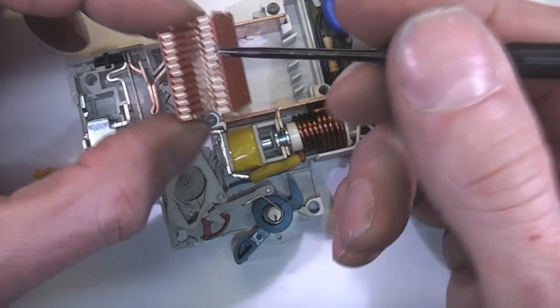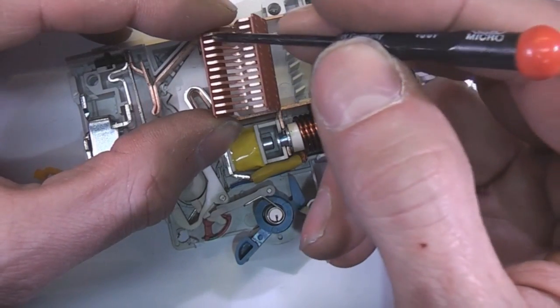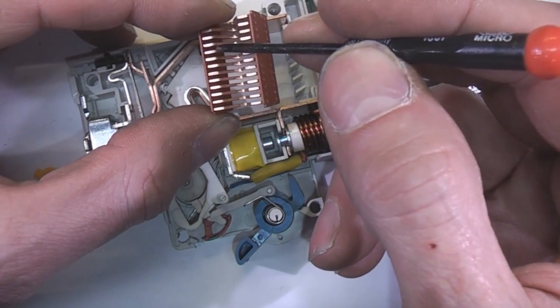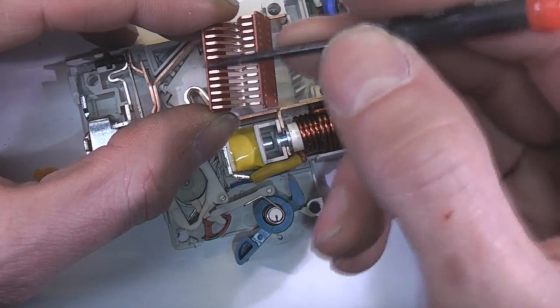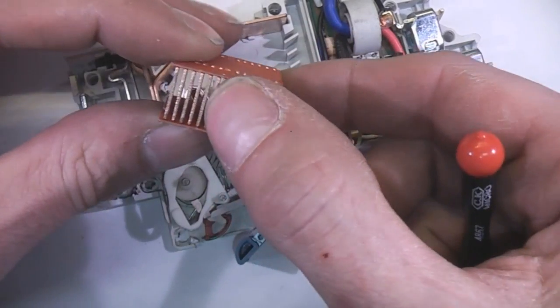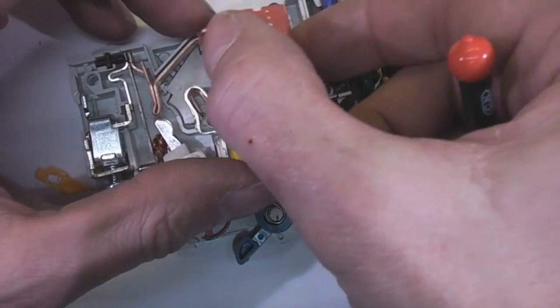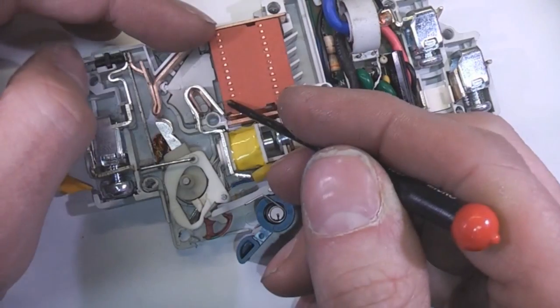And the idea is that once it hits here, the distance is actually quite small. So what you'll get is lots of small arcs, so that energy is dissipated over a wide area. And because this is a fairly substantial chunk of metal, it will cool that air down to quench that arc as quickly as it can. So you need a massive amount of energy to actually sustain the arc within this area.